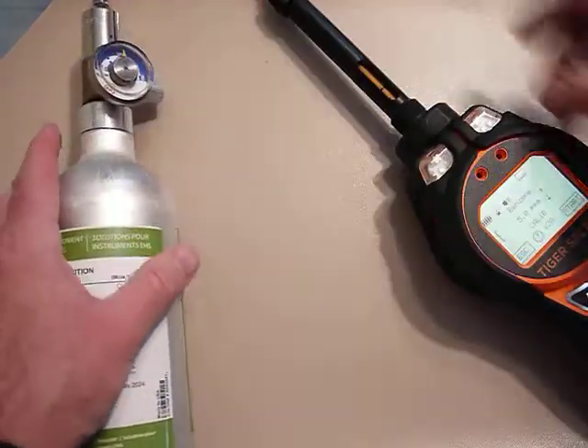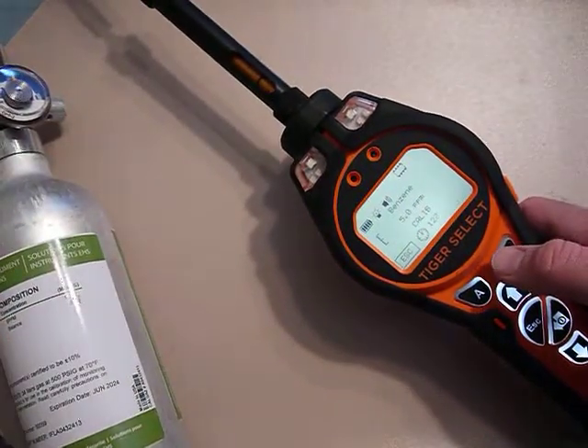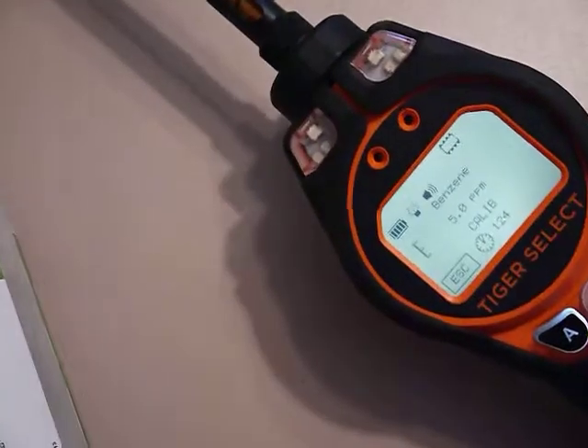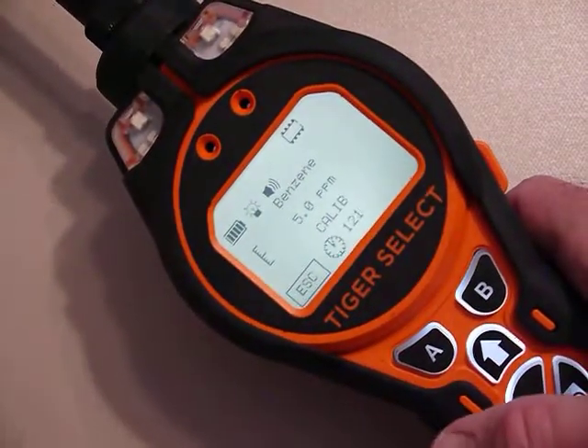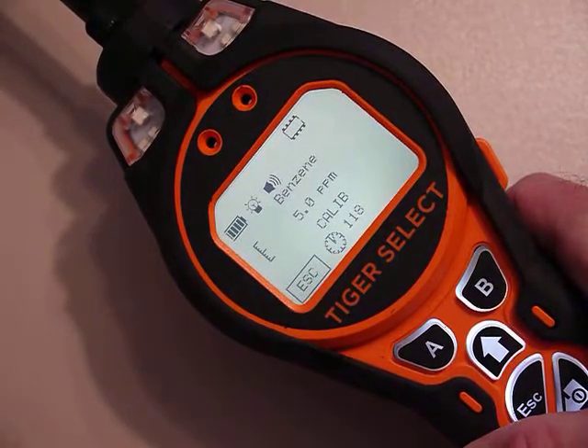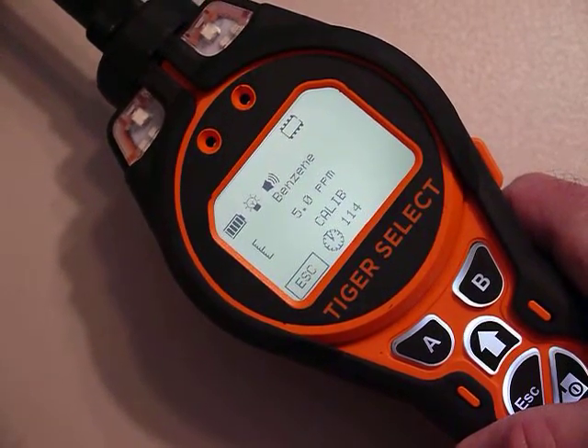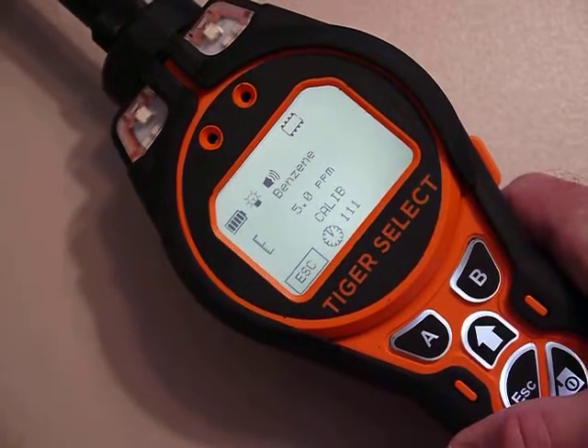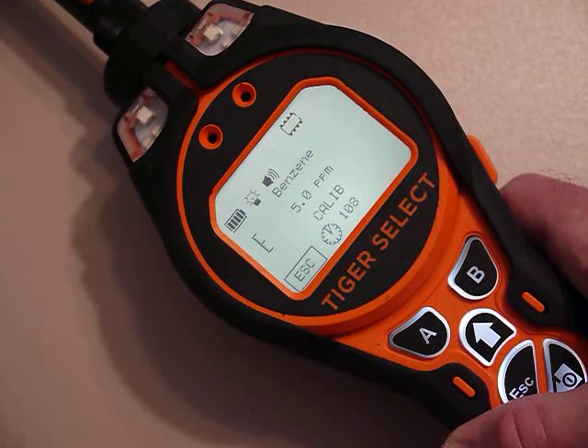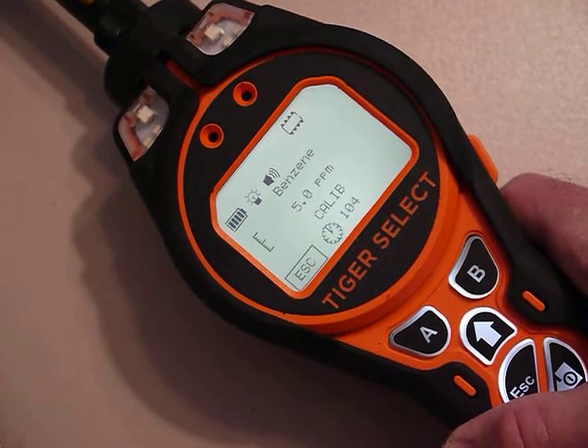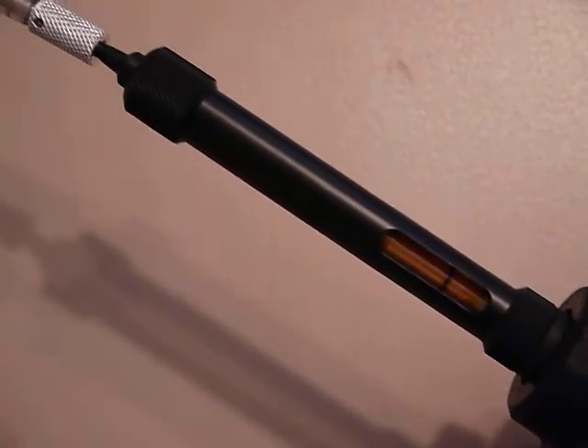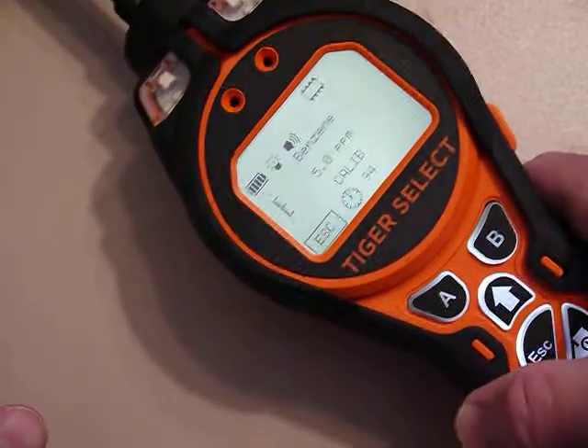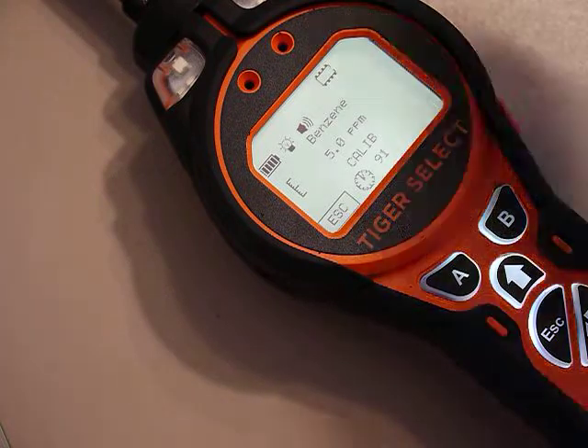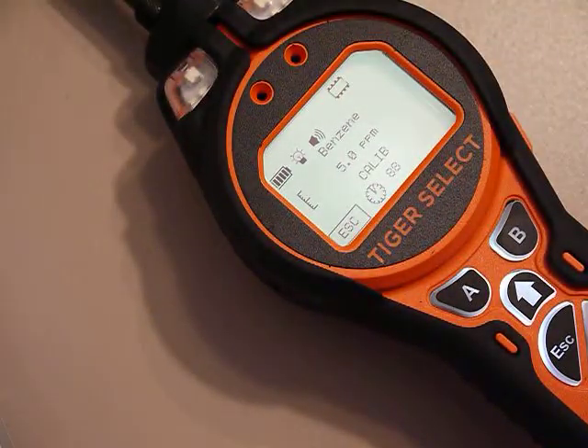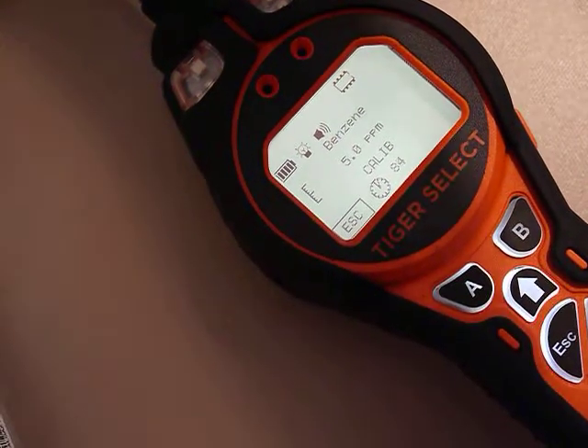So we've got 5 ppm flowing at 0.5 liters per minute, and I hit start, and the calibration will start. And I'll try to zoom in on this. So I've got 0.5 liter per minute of benzene flowing. There's a little silver piece on the end here. I'll try to show it here. Excess gas is coming out of a hole in that little silver piece, so it's not pressurizing the system, and we're pulling 5 ppm benzene through the meter to calibrate it. Meter's counting down. There's another 84 seconds left.